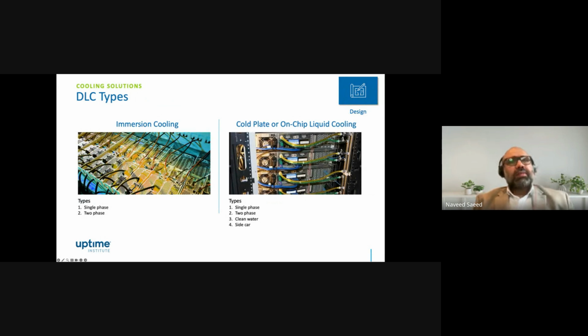Then there are further types of liquid cooling in each category. Immersion cooling has two categories, broadly speaking: single phase and two phase, and even within single phase there are multiple types of single-phase liquids, and in two phase there are multiple types of two-phase liquids. So then you have to look further into which kind of technology you are adopting, what the material compatibility of those liquids is with the equipment that you're purchasing or will be buying, and what the roadmap of your organization is to do that. These are things which have never been a problem in the past, but these are challenges that need to be solved by data center professionals in the new era.